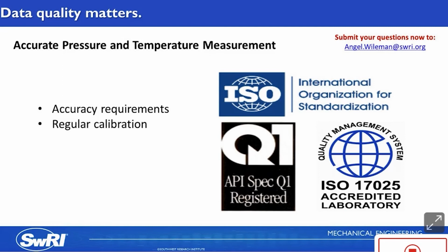The instruments should be calibrated at regular intervals, and I would recommend a maximum of 3 months for pressure transducers and 6 months for thermocouples or temperature transducers. However, if an instrument starts looking like it's near the end of its accuracy band, you should increase your calibration frequency. And really, the best practice is to calibrate instruments before and after each test, even if it's still within the calibration window. That way, if something comes back out of range, you can immediately notify the valve manufacturer.